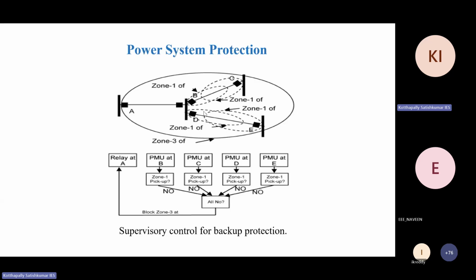But as I told you, in 2013 what happened is that because of the overloading, zone 3 operated. It is not a fault, it is simply an overload. These two are not operated, and this one got operated. That leads to tripping. So using PMUs, that can be avoided. It will check whether zone 1 has picked up in PMU B, PMU C, PMU D and PMU E. If not, it will block zone 3 of relay A. So it says zone 1 of B or zone 1 of D, or zone 1 of C or zone 1 of E has not operated, so here zone 3 should not operate.